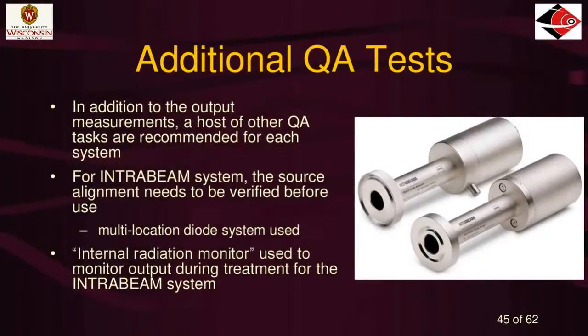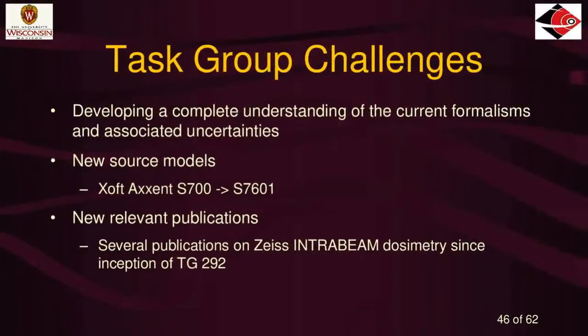For other QA tests, every time you treat with one of these systems you have to do additional tests. The IntraBeam requires aligning the drift tube — it can get bent, so you have to make sure it's straight for the day. There are also internal diodes to check output each day, similar to how Xoft uses a well chamber. A host of QA tests are recommended for each system, and the manufacturer provides a list of what you're supposed to do.